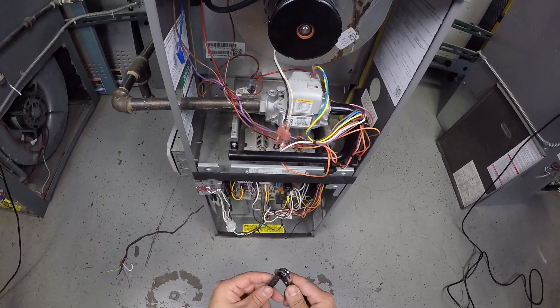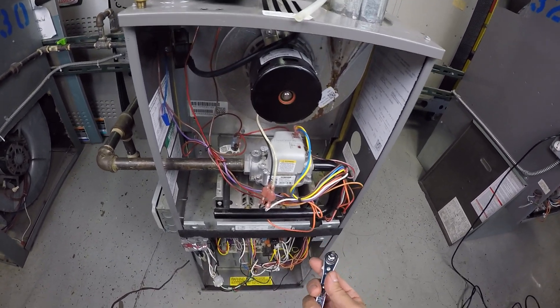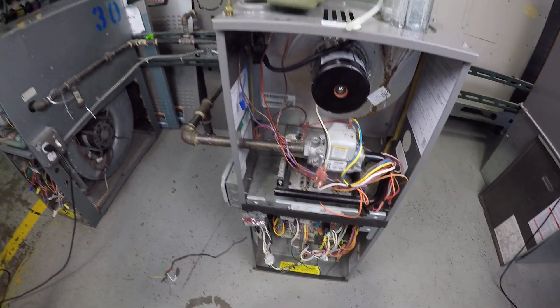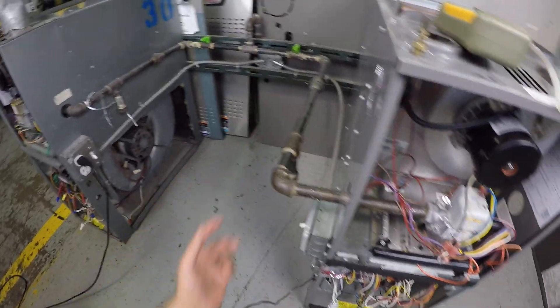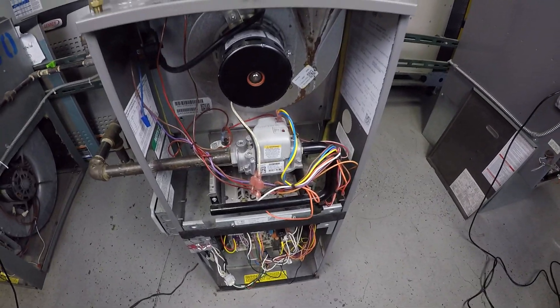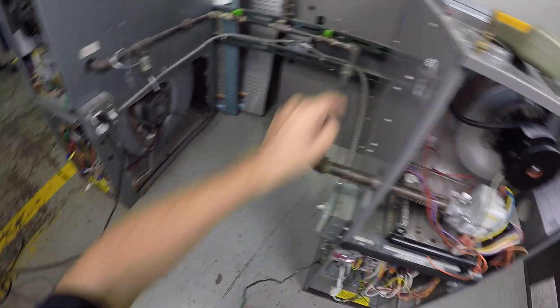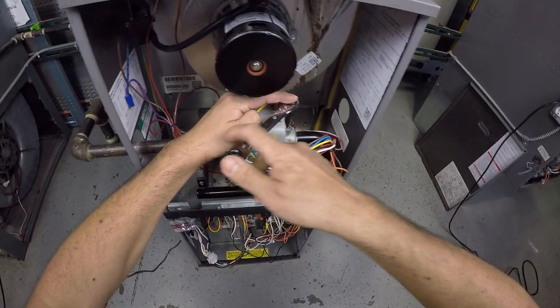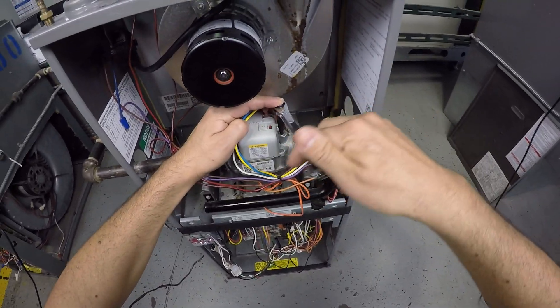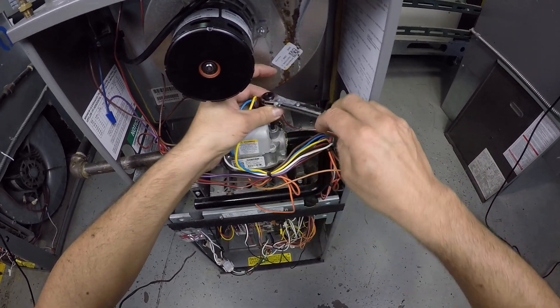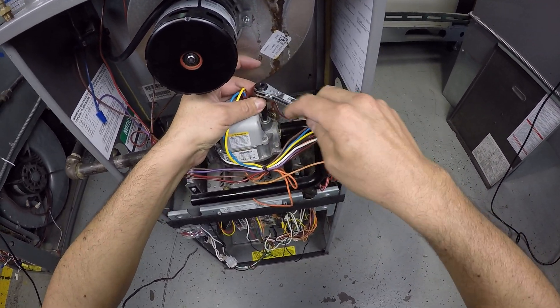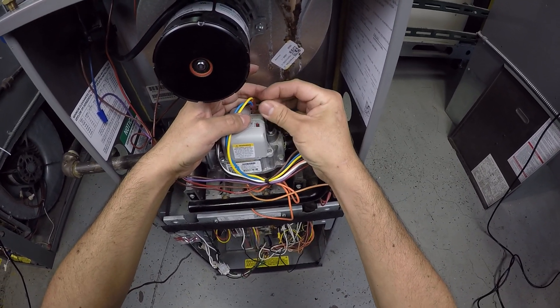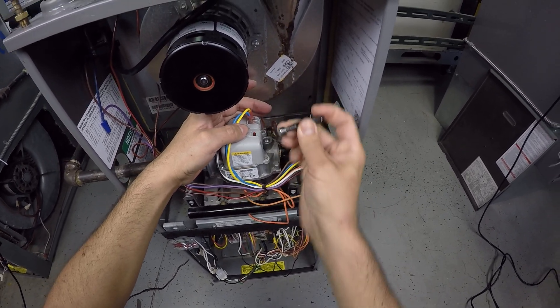Now, we're going to check the gas pressure coming out, or what they call the manifold pressure. To check the manifold pressure, it is kind of important that you also have your gas closed. Because of safety, let's just keep that closed. And now, we're going to remove the cap on the other side of the gas valve. I loosen up the cap, remove the wrench, and I use the fingers to remove the whole cap.